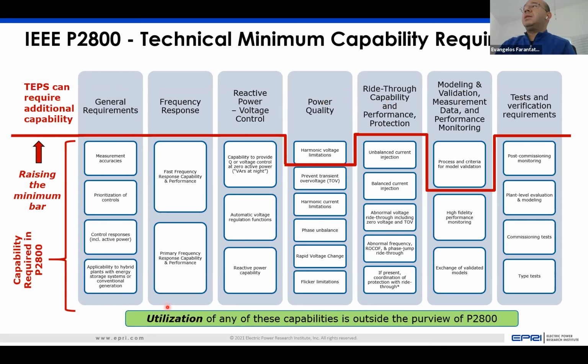I want to emphasize that this standard doesn't address or discuss anything about utilization of these capabilities. Utilization is up to the utility that performs the interconnection studies and sets the interconnection rules specifically. For example, the standard says that during a fault you should have the capability to inject positive sequence reactive current and negative sequence reactive current. It won't tell you how much, for how long, or the specifics, but it requires the capability of doing that.